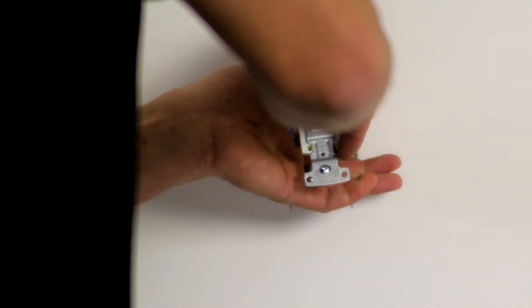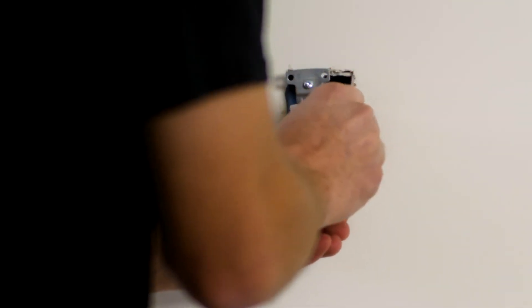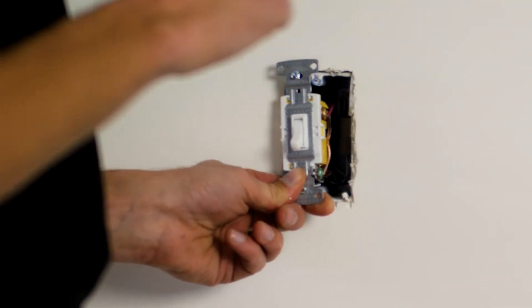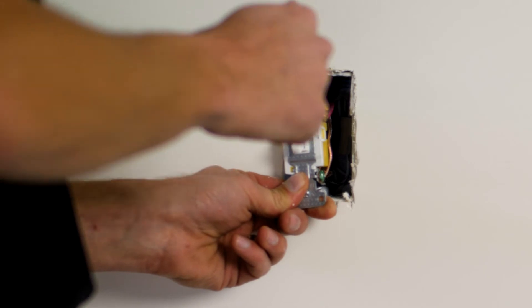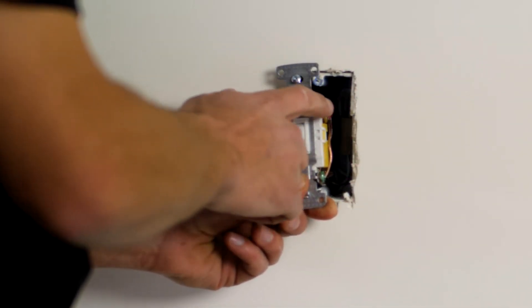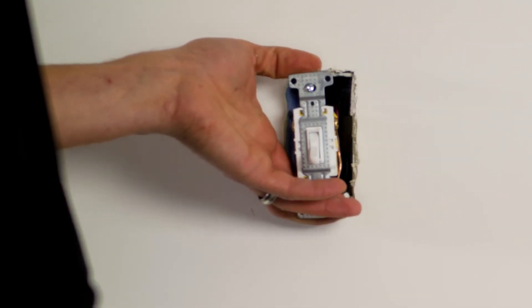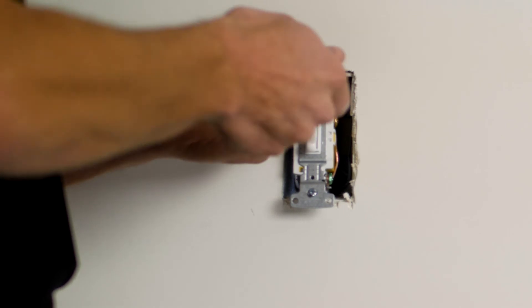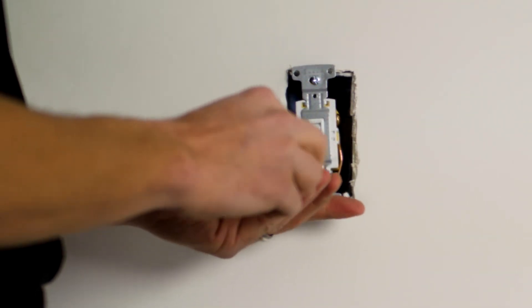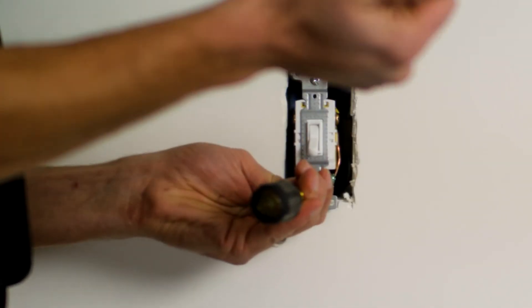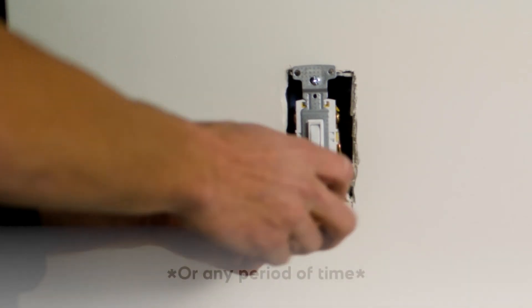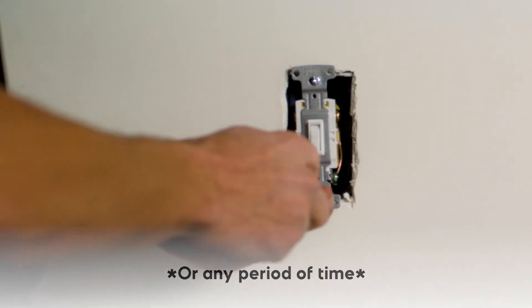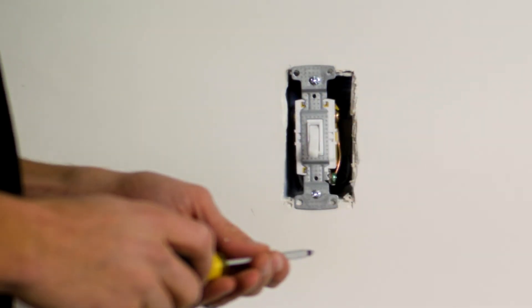I'm going to tuck and fold all of the conductors together. I'm going to watch out for my grounding conductor. At this point, my grounding conductor is real close to one of my travelers. I'm going to be very intentional every single time I execute the installation of a device to make sure that grounding conductor is pushed back or tucked away from any of the live conductors or terminals. Otherwise, I could end up with a dead short or, worse yet, a high resistance short. A high resistance short is where I've got a poor connection from hot to ground, but there is a connection nonetheless. In that case, rather than having an instantaneous trip on the breaker, what you'll experience is a slow trip. Lights will be on for 15 minutes, everything's working fine. After 15 minutes of slowly drawing over-current and heating up that breaker, you'll experience a trip and suddenly everything goes out.